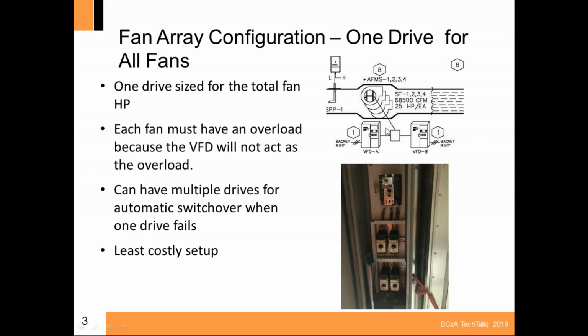Now the drive usually acts as an overload for the motors on your fans. Well, since we have one drive feeding 4 fans, we have to have separate overloads. In the picture on the bottom right, I took a picture of the inside of a cabinet. This is the line coming in to the disconnect right here, and then you have the 4 overloads down below it: overload for fan 1, fan 2, fan 3, and fan 4. These overloads are independently set based upon the overload of each individual motor on the fan.